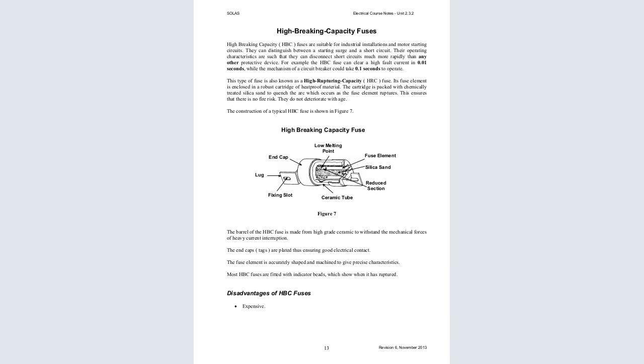Now, this type of fuse is also known as the high rupturing capacity or HRC fuse. Its fuse element is enclosed in a robust cartridge of heat-proof material. The cartridge is packed with chemically treated silica sand to quench the arc which occurs as the fuse element ruptures. So this ensures that there is no fire risk. They do not deteriorate with age.